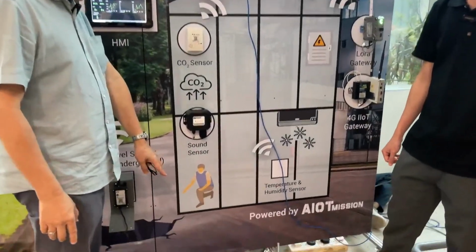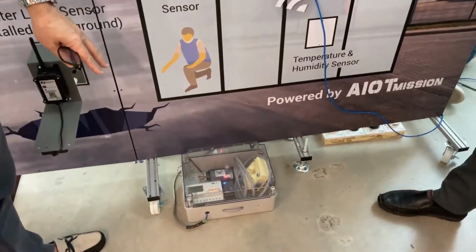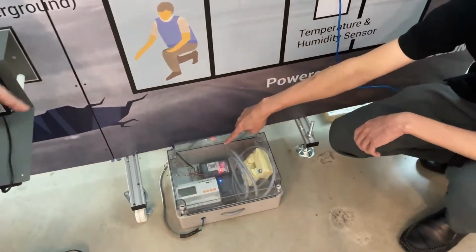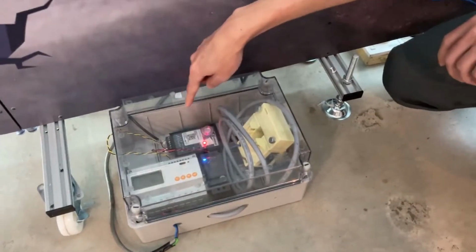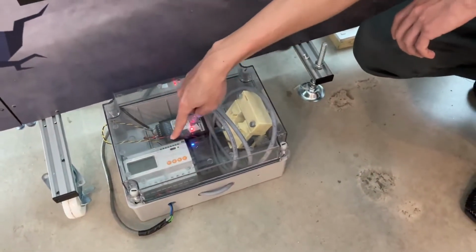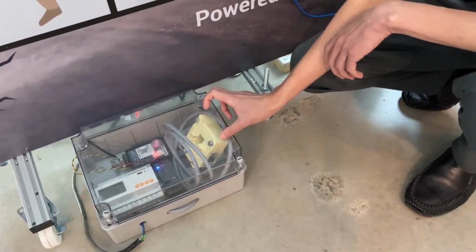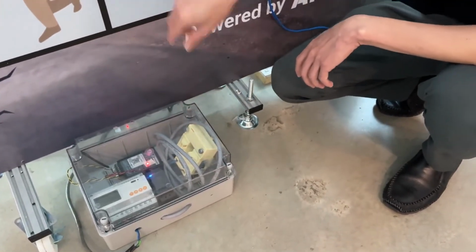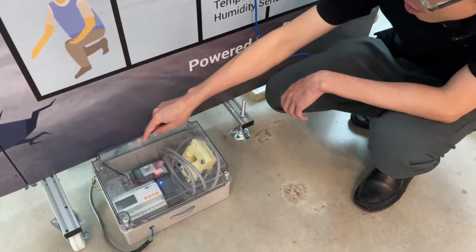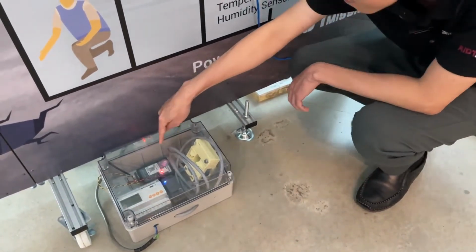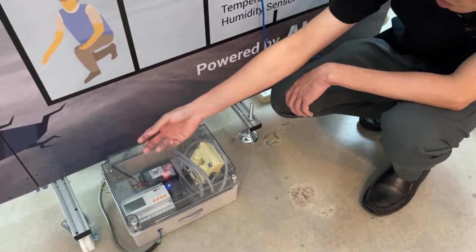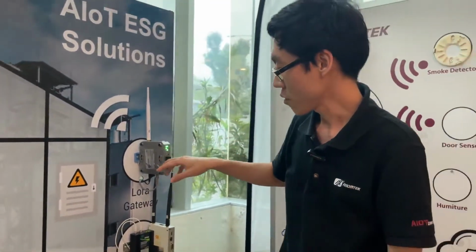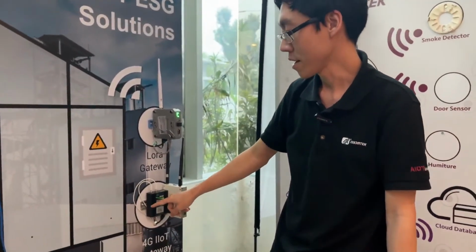So this part is also covered by one of the LoRa converters, which takes data from the power consumption. Maybe you can explain a little bit more. So this one is the LoRa converter. This one is the energy meter or the power meter. And over here we have a current transformer. If you put a wire through it, we can measure the current consumption of this system. All this data you can send through the antenna inside. After you collect the data from the meter to LoRa, it will send to the LoRa gateway over here, and then the LoRa gateway will send the data to the cloud through our 4G router.